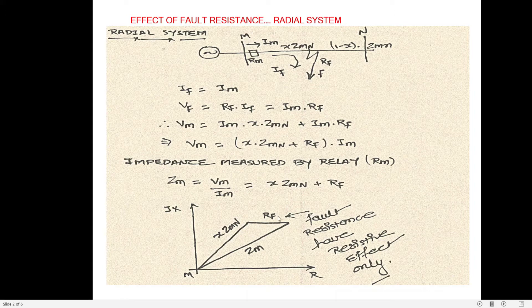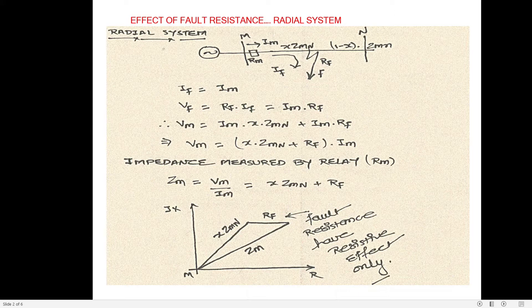It may happen that with a circular characteristic the measured impedance ZM does not fall inside the characteristic and the relay fails to operate. To avoid this, it was stated in the first session that mho relays, plain impedance relays, and offset mho relays all have limited fault resistance coverage. Therefore, a quadrilateral characteristic must be used because it provides higher resistance coverage.